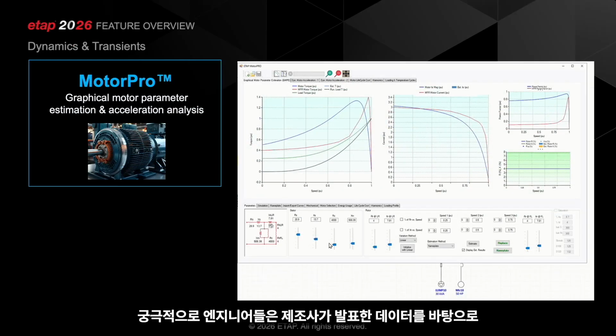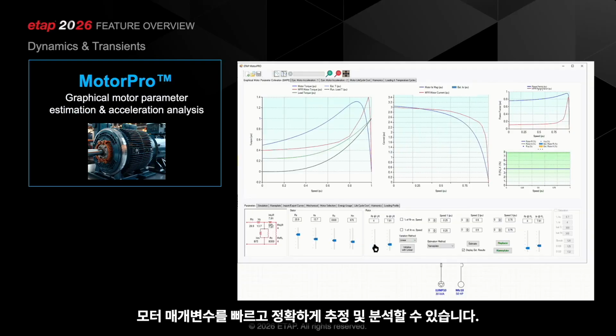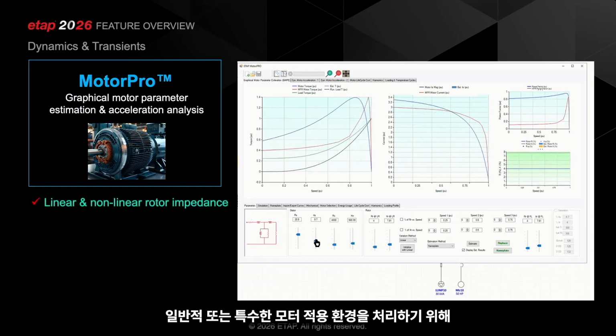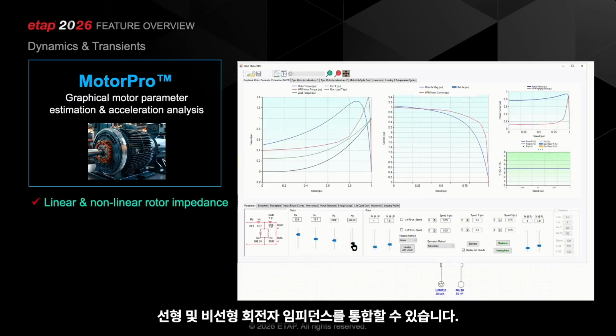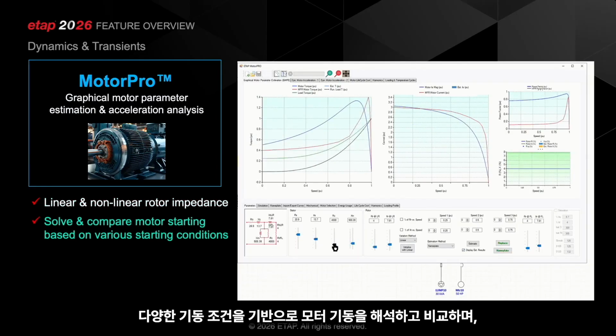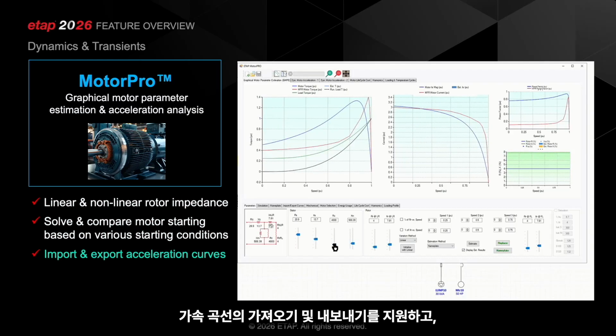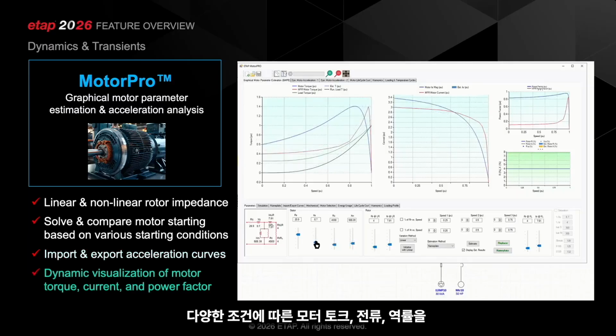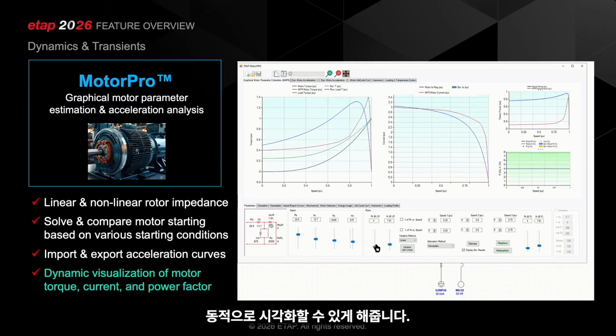Ultimately, engineers are able to quickly and accurately estimate and analyze motor parameters based on manufacturer-published data, incorporating linear and nonlinear rotor impedance to handle typical or special motor applications. Solve and compare motor starting based on various starting conditions. Import and export acceleration curves. Dynamic visualization of motor torque, current, and power factor based on various conditions.